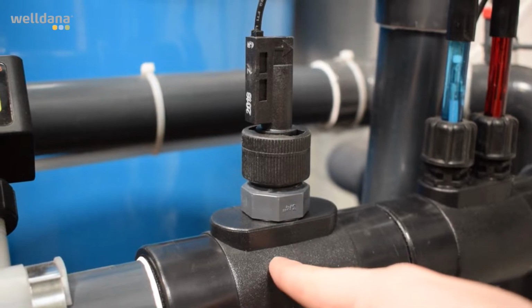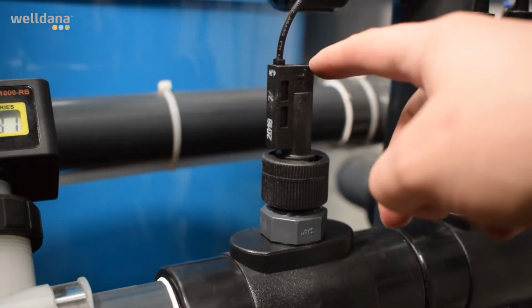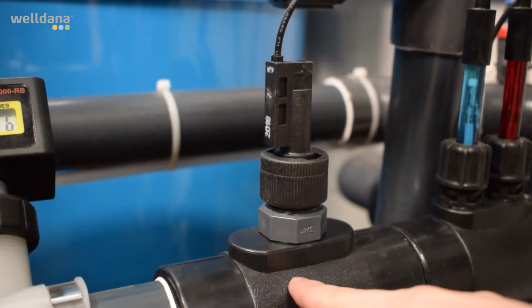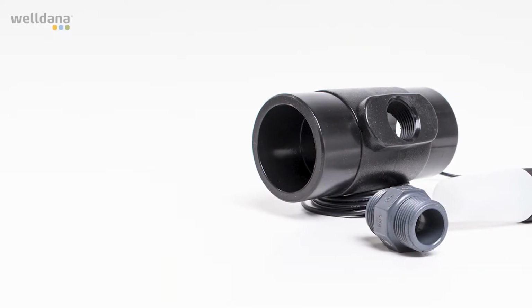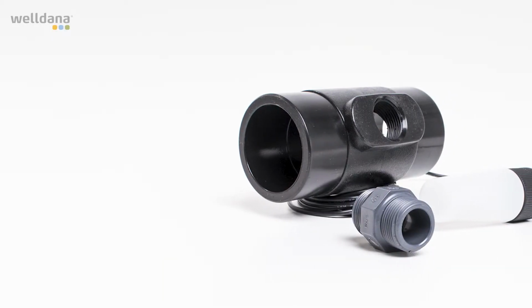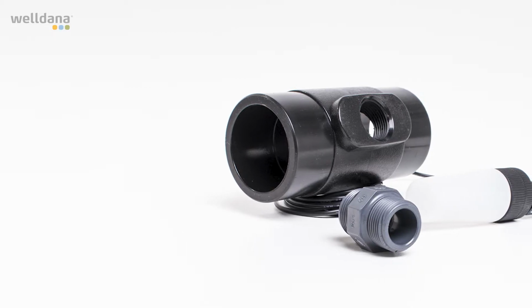The flow control is also an accessory. It prevents the acid pump from dosing when there is no flow in the pipes, for example when the filter pump is off. The flow control comes with all the fittings you need for mounting.